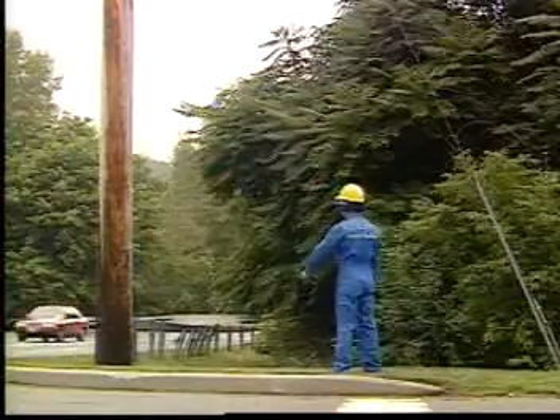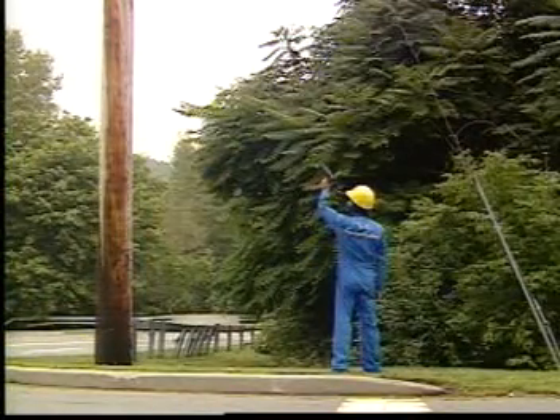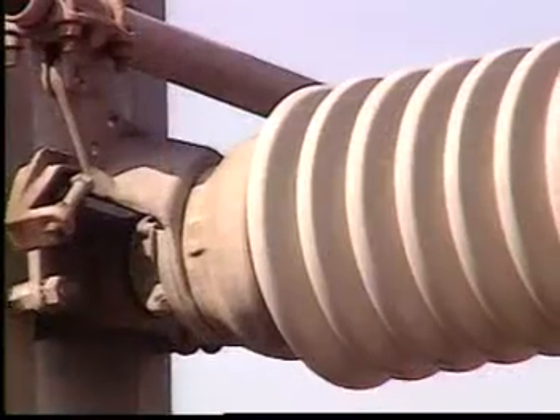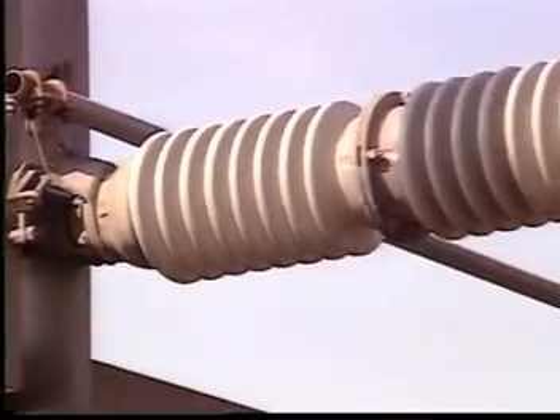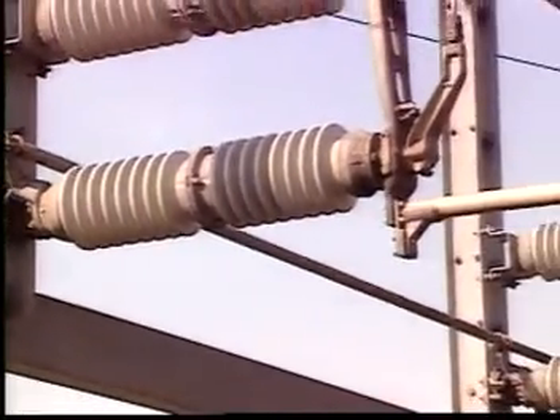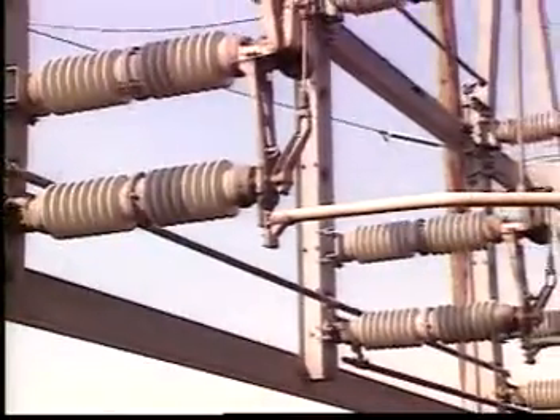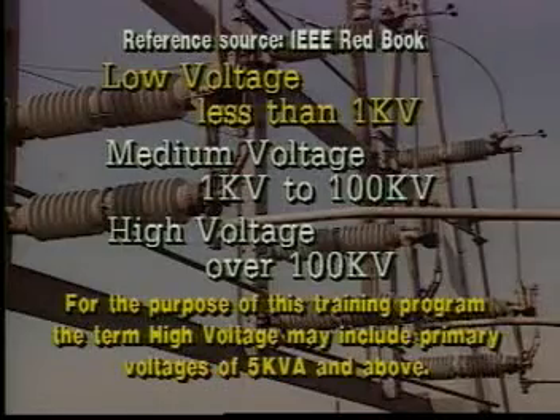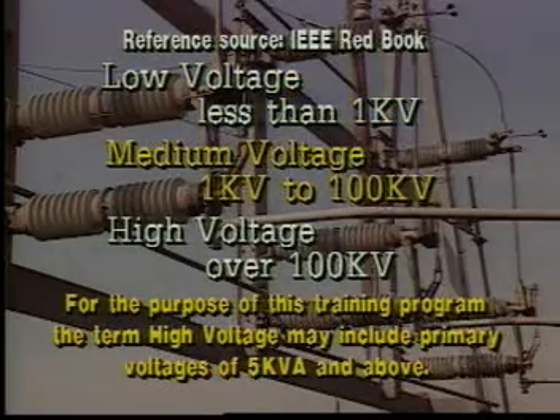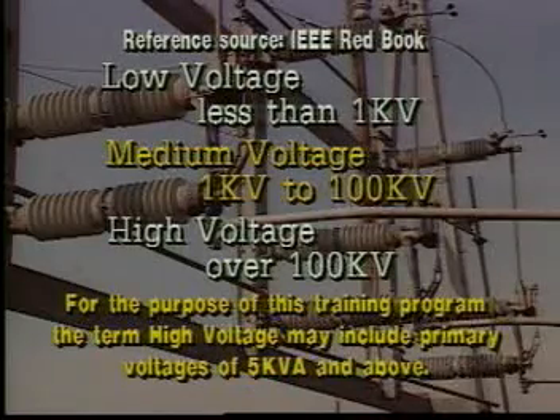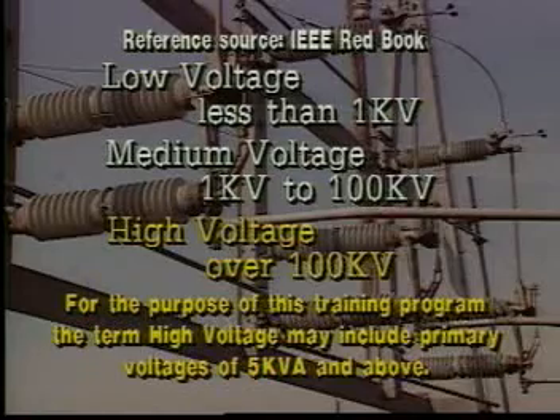In theory, we can test any equipment for arcing, tracking, and corona. However, most applications tend to be in the high voltage range. To clarify what we mean by low, mid, and high voltages, we'll use these generic voltage definitions. Low voltage is less than 1,000 volts. Medium voltage refers to the range between 1,000 and 100,000 volts. And high voltage means anything over 100,000 volts.